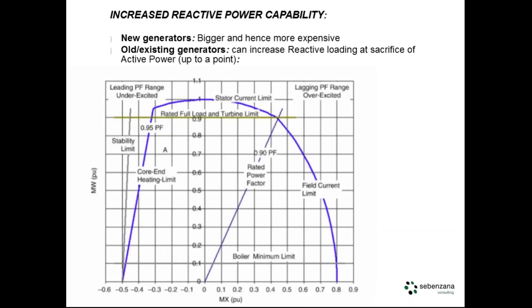In terms of increased reactive power capability: on new generators, in order to handle that, they're just going to have to be bigger — hence more expensive. For existing ones, you can increase your reactive loading, but you might have to sacrifice active power. From a standard capability diagram: this is importing VARs, exporting VARs, and this is your rated full load operating limit based on the turbine limit. If you're operating at rated power factor at maximum active power and someone asks you to go from 0.4 per unit to exporting 0.7 per unit megavars, you can do it, but in order to comply with the rotor heat limit you'll have to decrease power along the curve — by the time you get to 0.7 per unit VARs, you're sitting at 0.5 of your active power — a 50% power reduction.